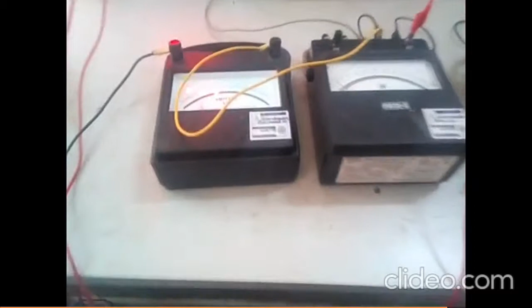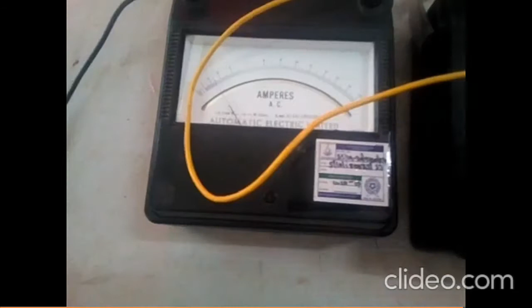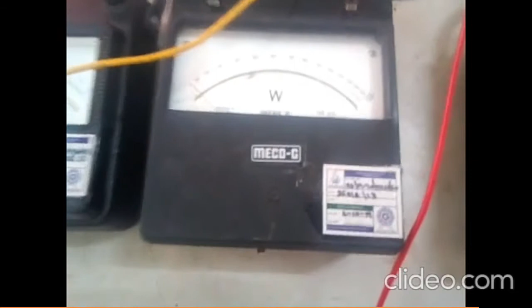After applying rated voltage to the induction motor, it starts rotating at its rated RPM, that is 1500 RPM on no load. After that we take the meter readings, like voltmeter reading and ammeter reading. We observe the ammeter reading, that is the no load current, and we take the no load power from the 2 wattmeters, since we are using the 2 wattmeter method for measuring 3-phase power.